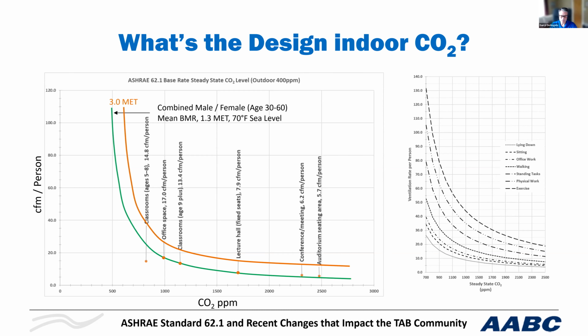So during COVID, I've been hearing everybody saying, hey, just maintain 800 ppm and you're going to be all set. Well, a lot of systems aren't going to be able to do that. For an office, okay, it's only 200 ppm different, it may be able to do that. But a conference room, which by ASHRAE Standard 62 is at 2,300 parts per million, that's quite a big difference.